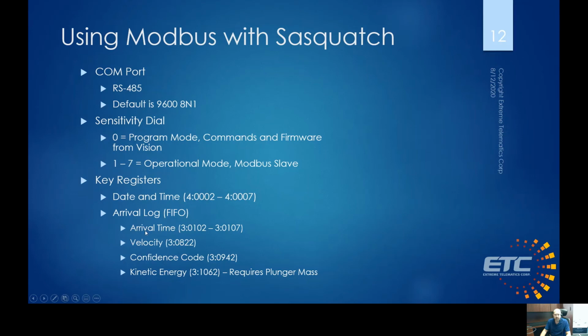There is 4 pieces of information. You get the arrival time and date, which is coming from this date and time register here. And then it obviously runs. The velocity of that arrival, a confidence code, and then we also give you the kinetic energy if you've set the plunger mass. Now you'll notice these registers are all spaced out because what we've done is we have all of the log entries, like there's a number of arrival times, so they're all stacked here and then spaced out. So then all the velocities, all the confidence codes, and all the kinetic energies.